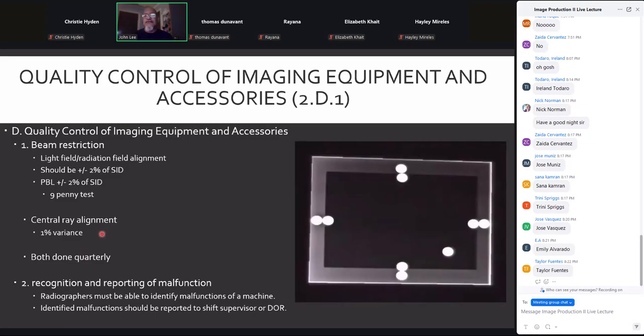Okay, these last 4 slides are quality control. The light field, radiation field alignment needs to be within 2% of the SID. You can use a special cassette for this, or you can go the cheap route and do the 9-penny test. Okay, you can use an 8-penny test. The point of the 9th penny, though, is to mark either cathode or anode, so you know what collimator is off. Now, the reason we use pennies, the reason we don't use dimes, nickels, or quarters, is because of that margin of error. 2% of the SID, plus or minus.